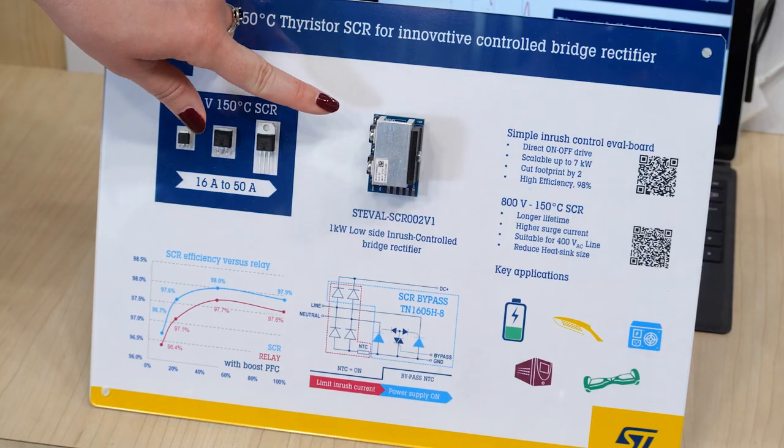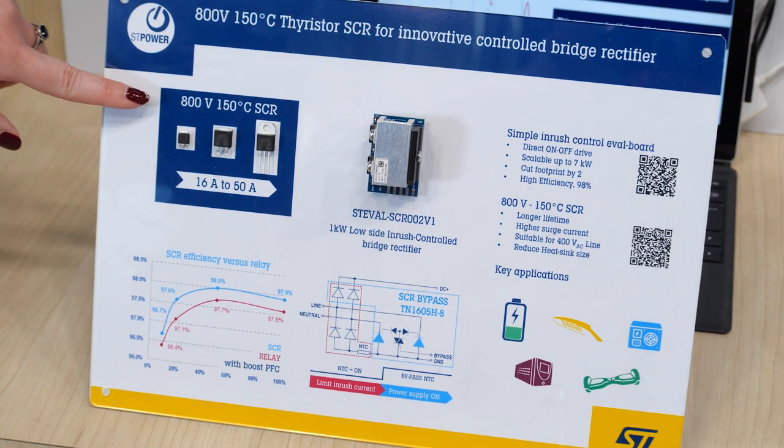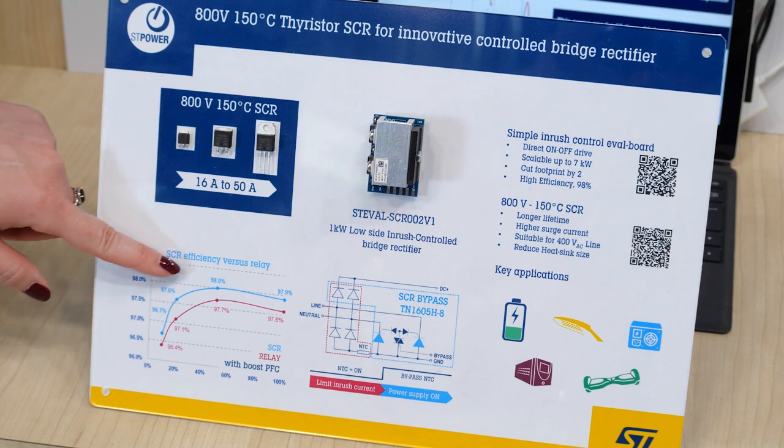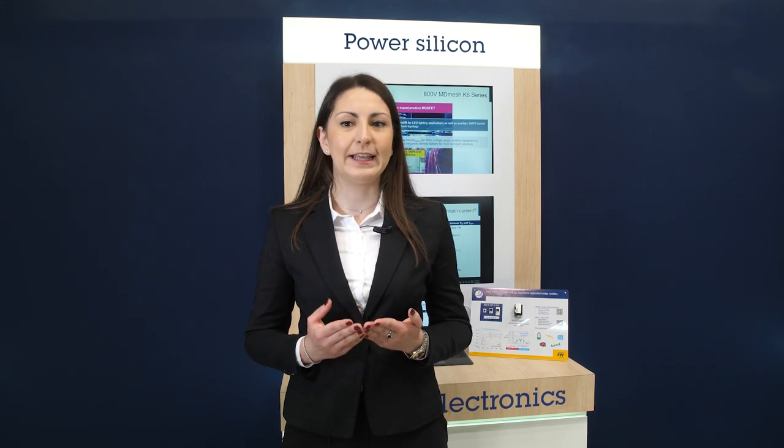The STEVAL-SCR002V1 can control inrush current using only the smart inrush method described. In this mode of operation, the board will not only avoid all previously mentioned drawbacks of mechanical relays, but will also improve the charge time of the DC capacitor and increase overall system efficiency for applications up to 1 kW.